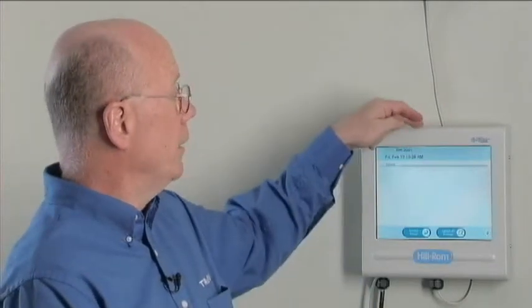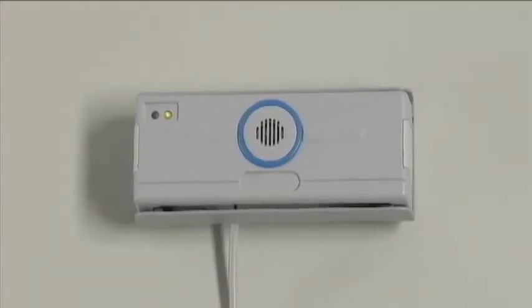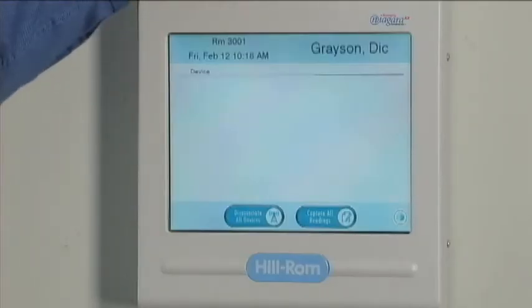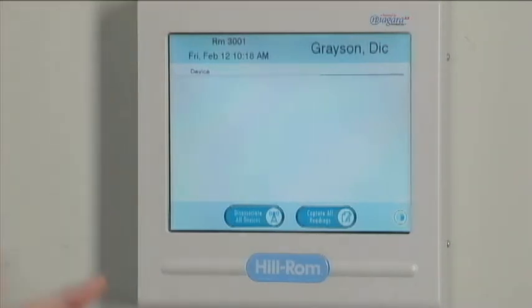We have a hub that goes in every room. An example right here is our hub that goes into a hospital room. If it's a private room, there'd be one in the room. If it's a semi-private, there might be two. And above or on the same wall as the hub, typically we have what's called a beacon. The beacon actually identifies the room, and the two are paired together. They have a common identifier, so anytime a beacon signal is detected by a medical device, it can use that information to then locate a hub in the room and begin to pass data to it wirelessly over the infrastructure that we have. So the typical operational scenario is the hub displays data that the clinician might be interested in.